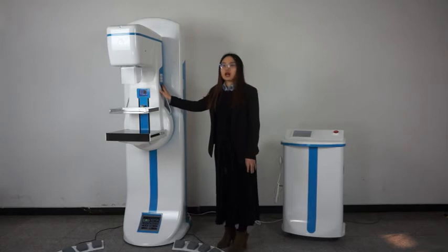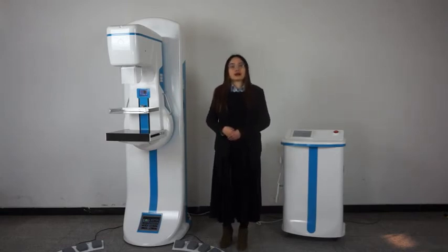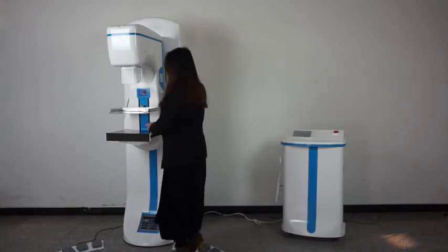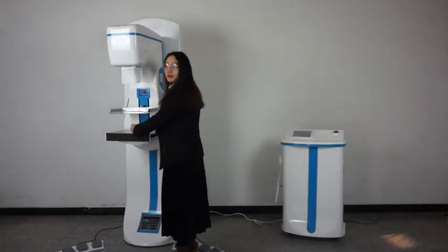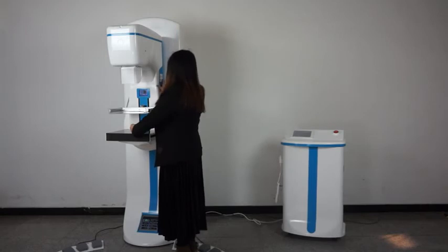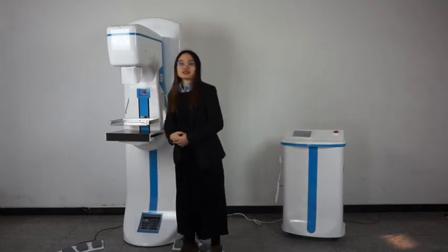There are 2 panels on the C-arm to control the movement of the compressor. We have core technology of 3-segment compression, which enables patients to have a comfortable examination experience. It works like this. First, you put the mammary gland on here and click the button here to move the compressor. At the beginning, the compressor will move down at high speed. When about to touch the mammary gland, it will slow down continuously and automatically in 3 segments with different pressure. It has greatly palliated the sufferings of patients.